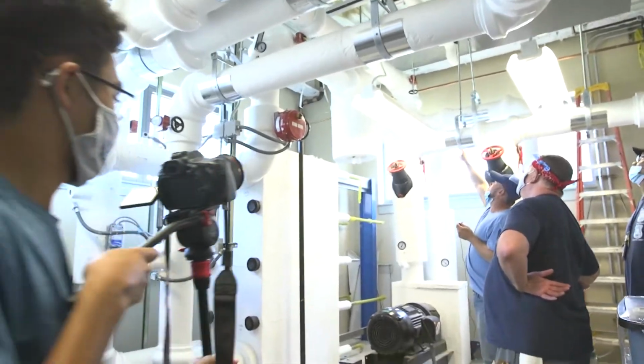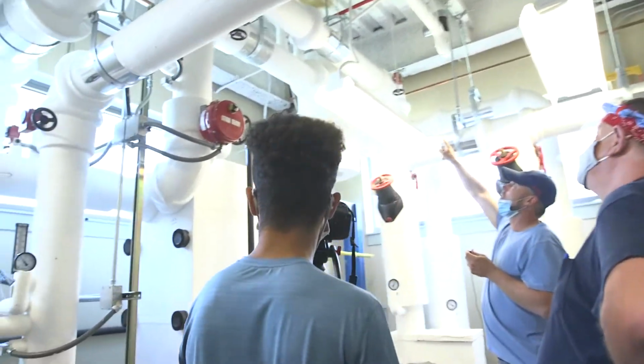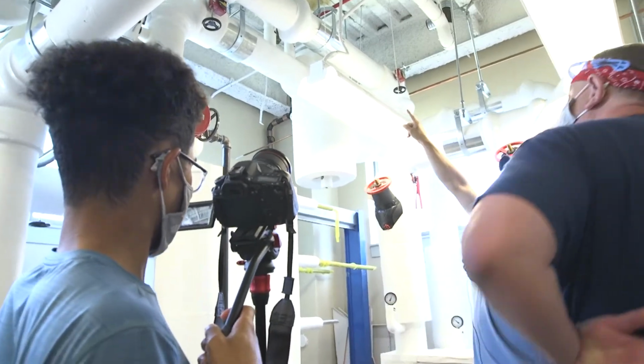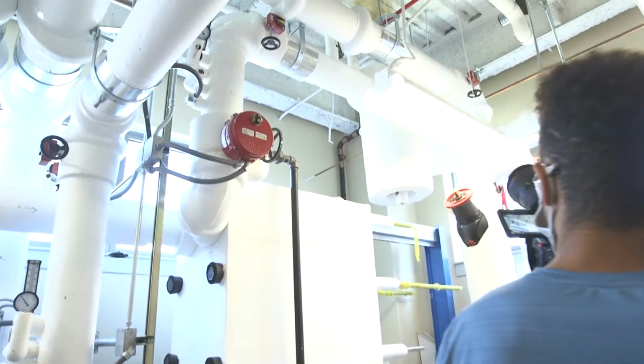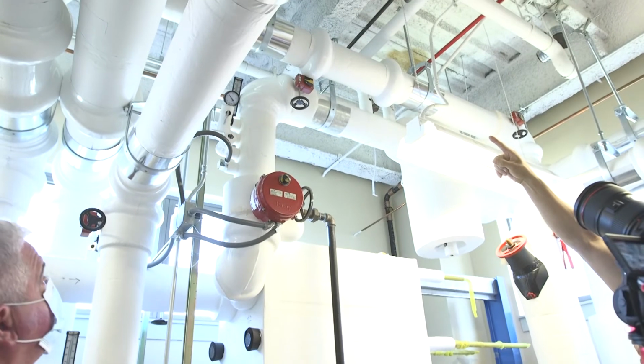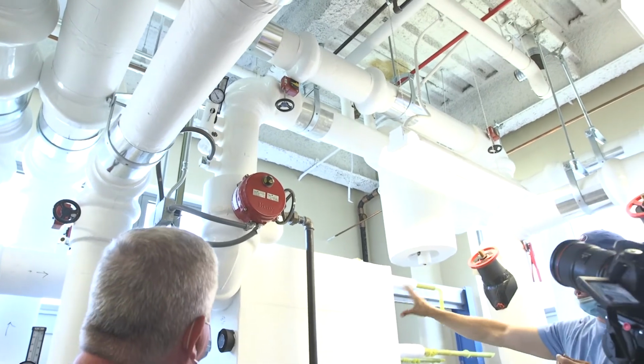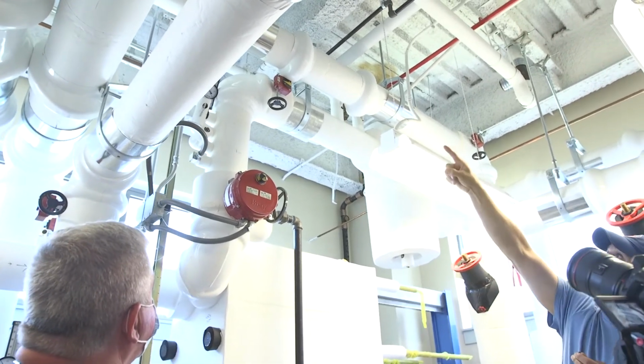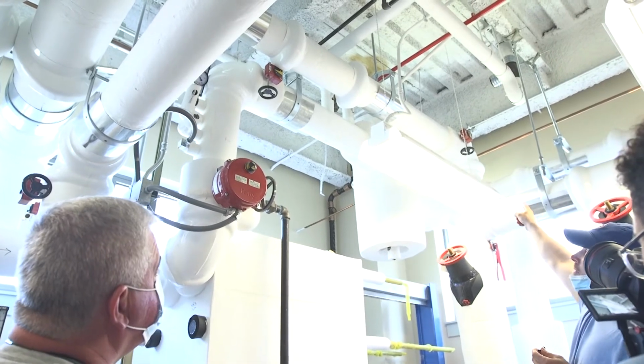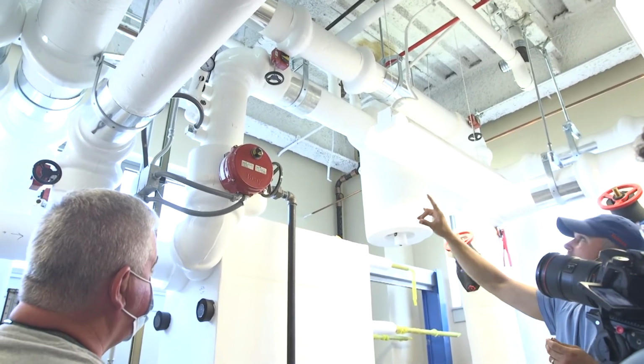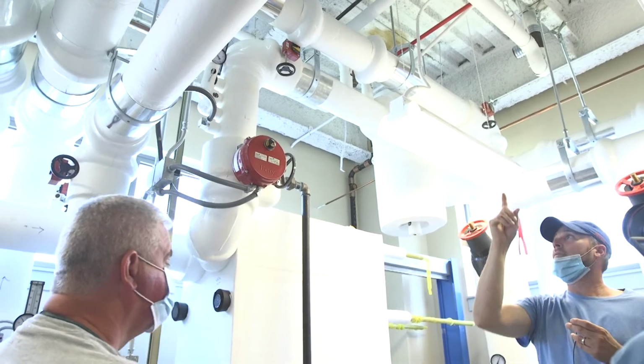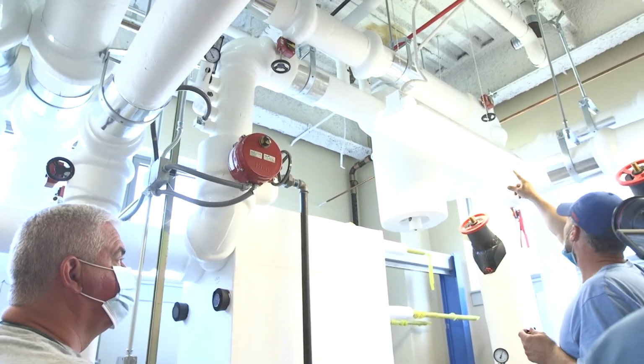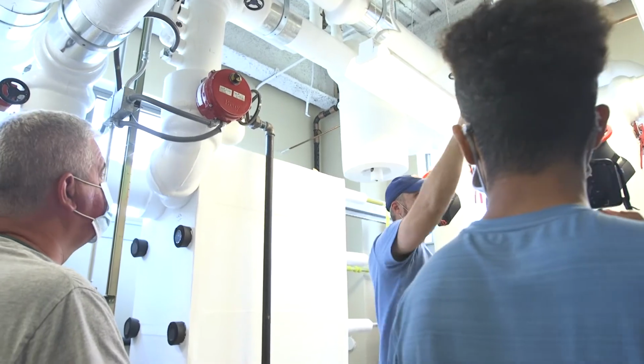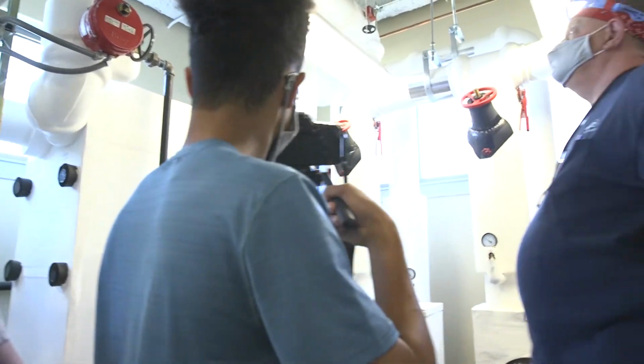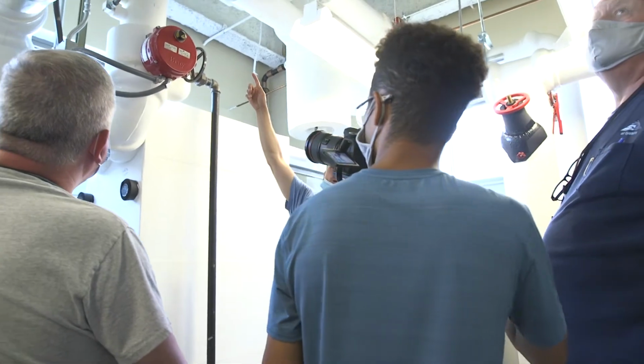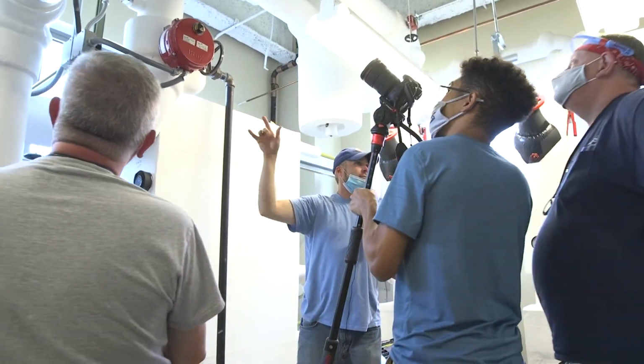This bypass line up here. Okay, you see it? With the round handle and the round handle. Two valves. So if this heat exchanger needed to come offline, you would open that valve and open that valve, and you could close the heat exchanger plant side valves, and your primary chill water would bypass this heat exchanger and go right into the suction side of the pumps and out. So if you ever have a problem with the heat exchangers, you have manual bypasses for both systems.